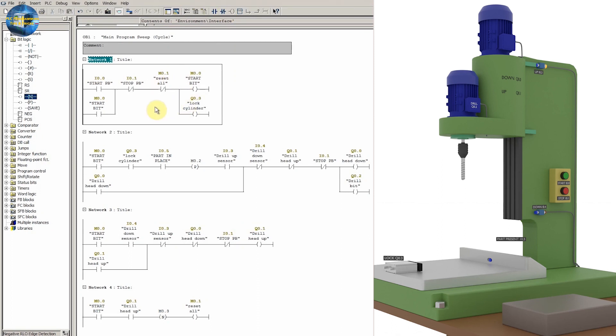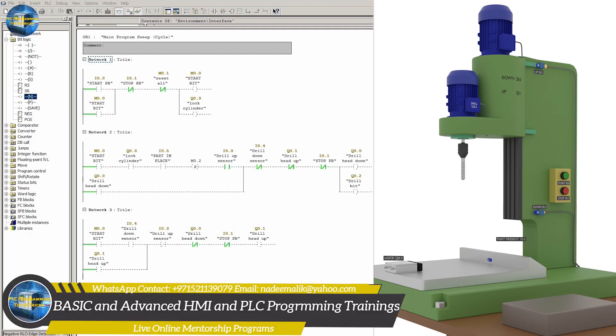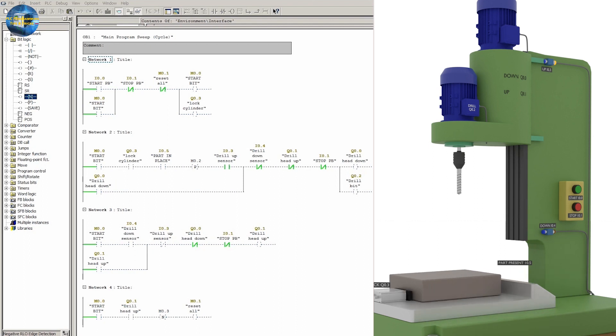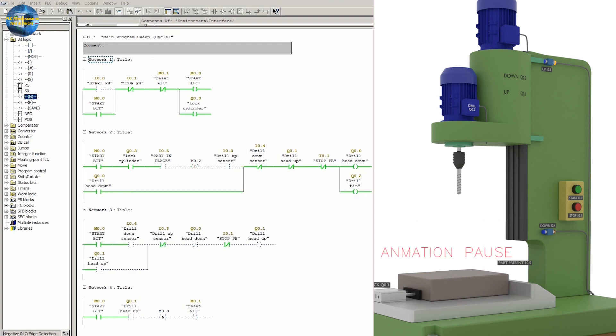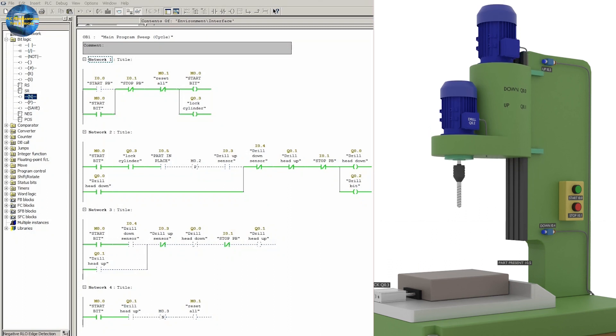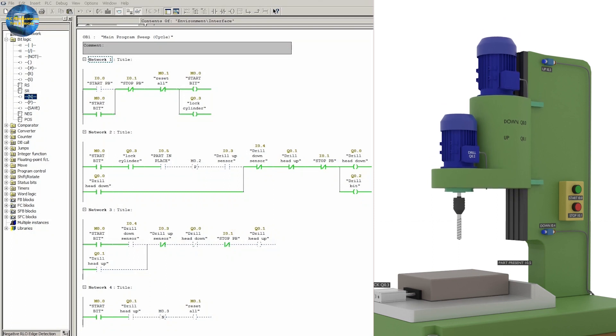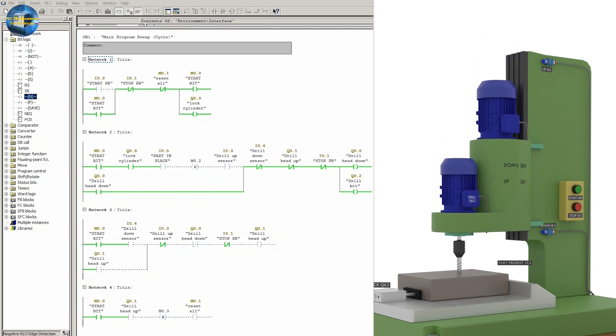We upload this logic into the PLC to test it. We place an object on the machine platform, and as soon as we press the start push button I0.0, the start bit M0.0 and cylinder Q0.3 turn on. The locking cylinder locks the object in place, confirmed by sensor I0.5, and it turns on drill head down output Q0.0 and drill bit motor Q0.2. The drill head starts to move down.